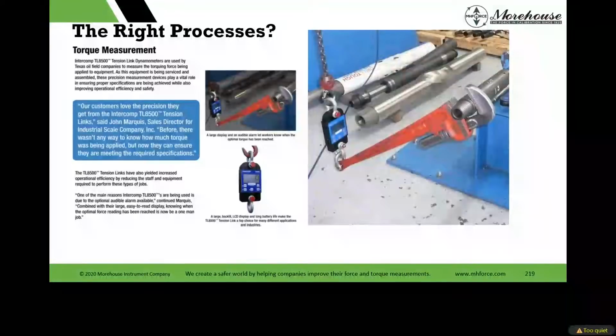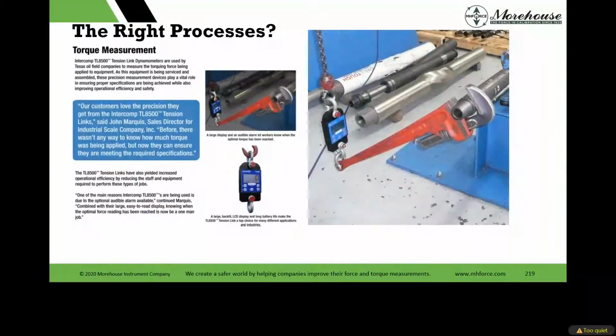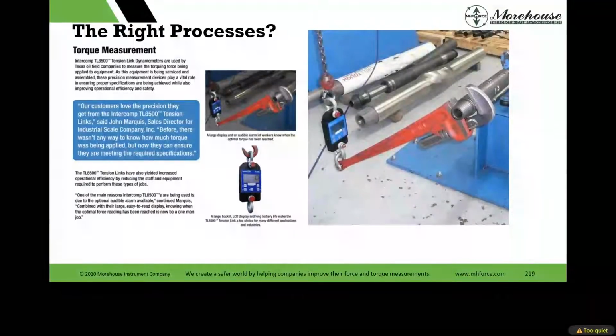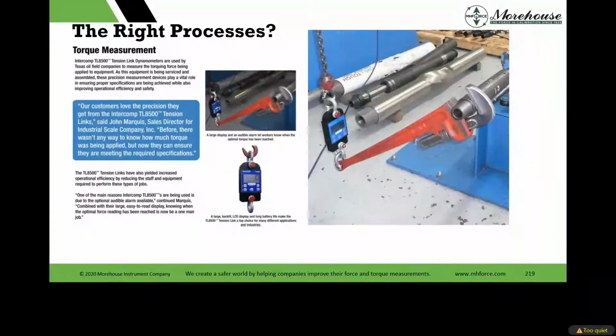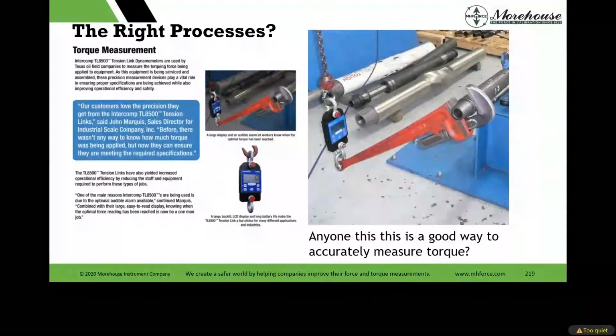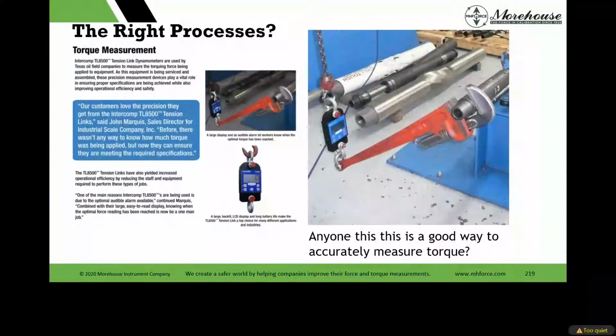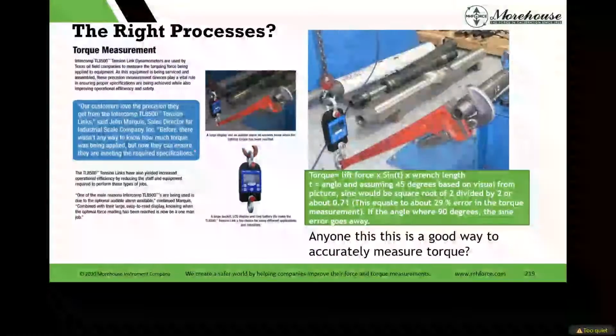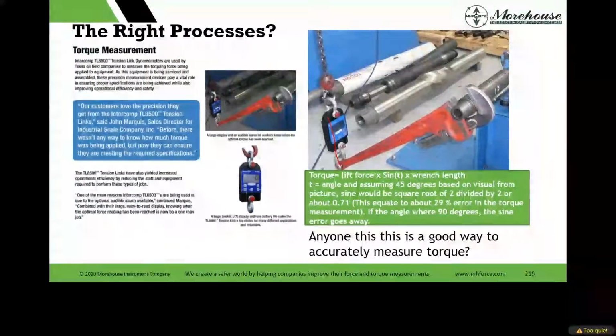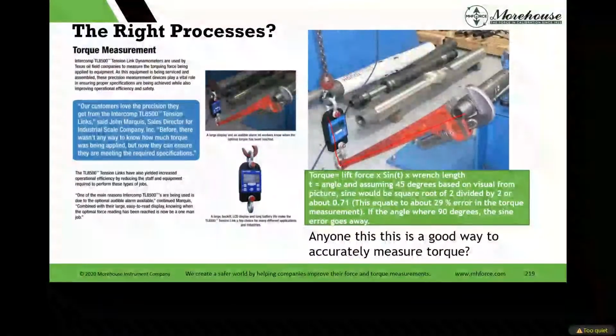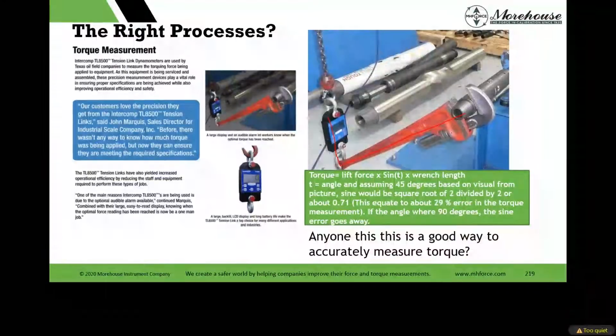So, with some funny stuff, this is marketing material I love, and I'm picking on Intercomp. This is still on their website. I'm going to pick on them until they take it down. Our customer loved the precision that they get with this instrument. Anybody making a torque measurement that thinks this is a good way to measure torque, likely not. But if you want to do the math, you can calculate the degrees here, and assuming 45 degrees, someone might say it's 30 degrees. The math comes out to about a 29% error.